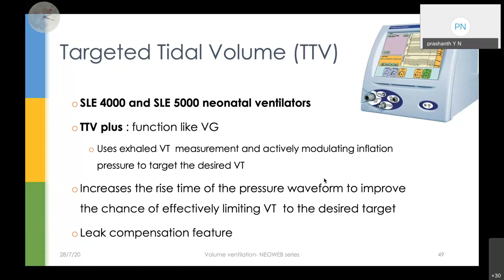Another added advantage with SLE is that they also offer a leak compensation feature. That is, when the ventilator senses that there is a leak, it actually gives additional volumes to compensate for the leaks. So this is what the company claims. But actually, when you use TTV plus, it's as good as using your volume guarantee.